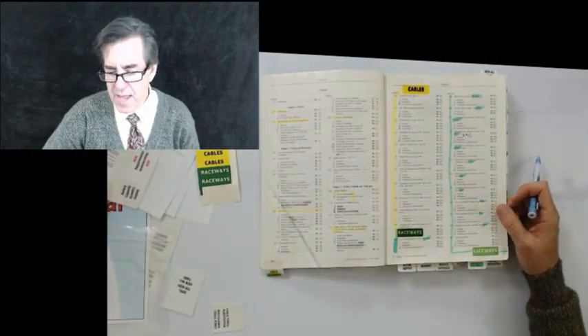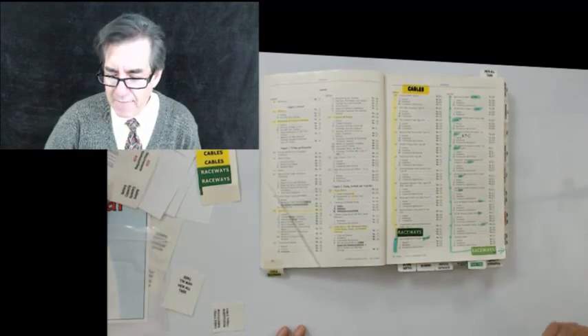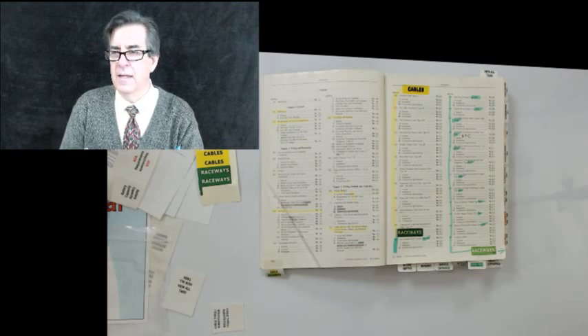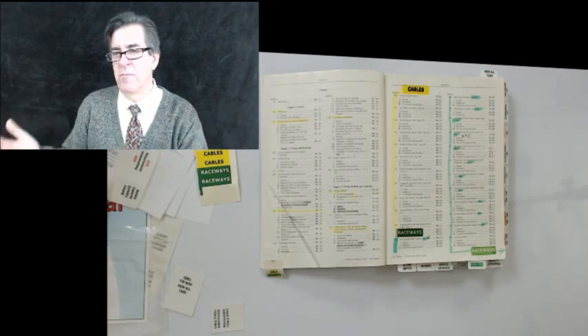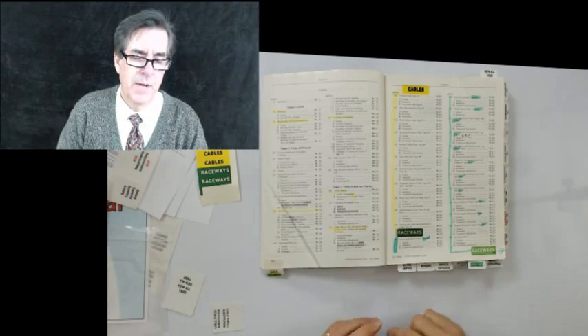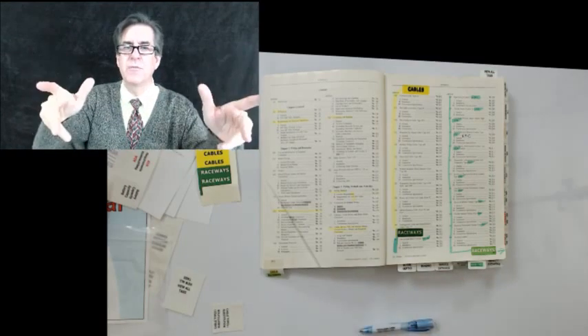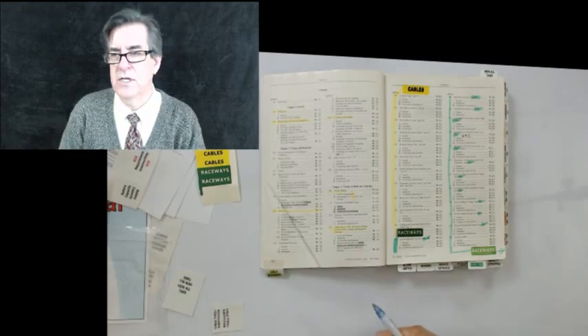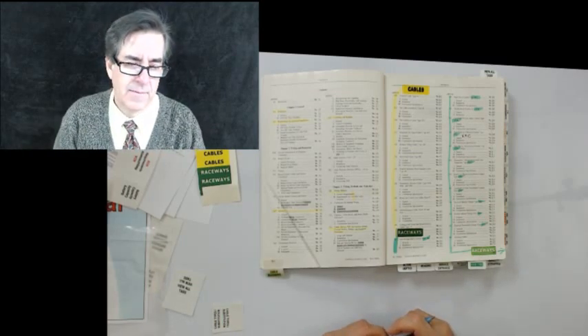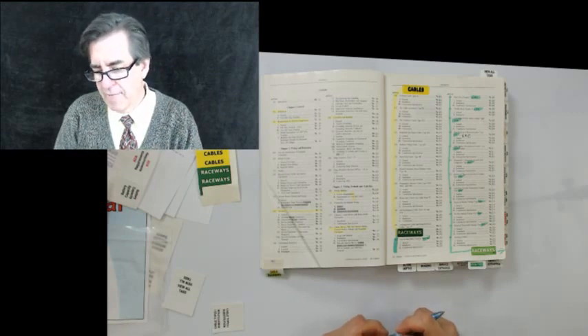Let me give you an example. In the question, they will ask you to do something with the raceway—define how often you have to support it, where it can be placed, where it's permitted or not permitted to be used, or how often you support the tube or the pipe. Because obviously, if it's a tube, it's flexible. You got to support it more often on a wall than you would on an actual metal pipe that's more stiff, right? Or PVC is flexible too, so you got to support that more often than a rigid pipe.